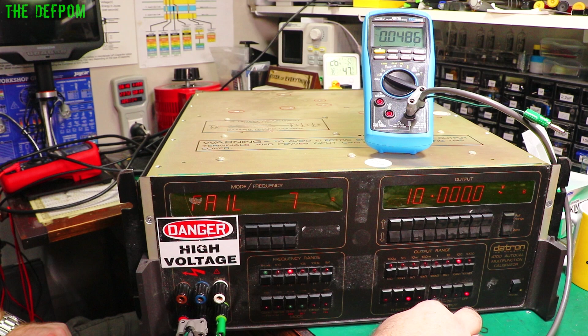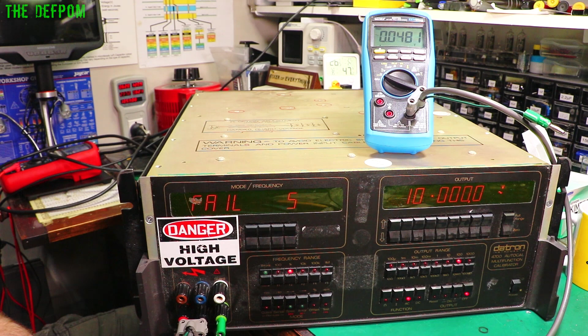I can at 0 volts. It stopped me from using a high voltage range. That's on, but there's not much going on. So 100 volt range, it's got an output. Oh, it's gone to DC. Output on. We're getting 9 volts that one, which is the error we knew about. Fail 5 again. Okay. Try and turn it back on. Won't let me. Do the reset and I get the fail 7. So those high voltage ones still aren't working, which is the original fault I saw when I first tried this thing out. Let's try resistance.